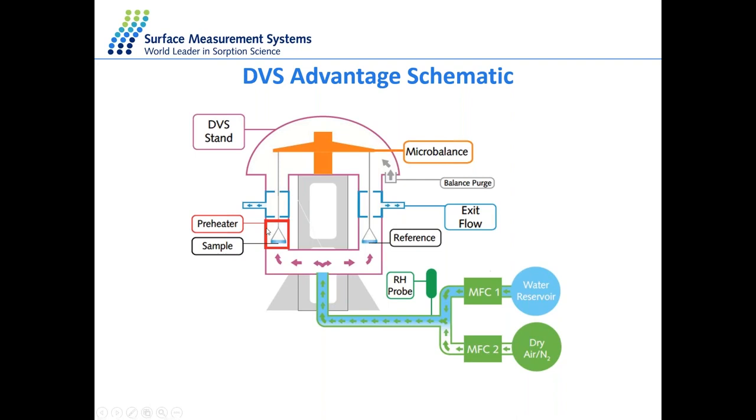So what we want to measure is only the mass change related to the sample itself. Now, the best way to do it is to just make it symmetrical. So if everything on the sample side is identical on the reference side, and the only difference is the sample itself, when we push molecules in the chamber, the only part that we measure is the delta, which is the sample itself. So that's basically the schematic I represent to show you how we collect data from a gravimetric perspective.